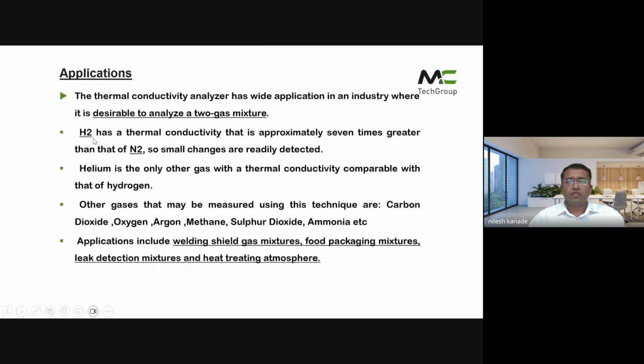Thermal conductivity analyzers have wide applications in industries where it's desirable to analyze two-gas mixtures, such as hydrogen and nitrogen, hydrogen and helium, or oxygen and nitrogen. Out of such a mixture, any one gas can be identified and measured using this kind of analyzer. Hydrogen's thermal conductivity is about 7 times greater than that of nitrogen, so even small changes are readily detected. Helium is the only other gas with thermal conductivity comparable to hydrogen. Other gases that may be measured using these techniques include carbon dioxide, oxygen, argon, and methane.